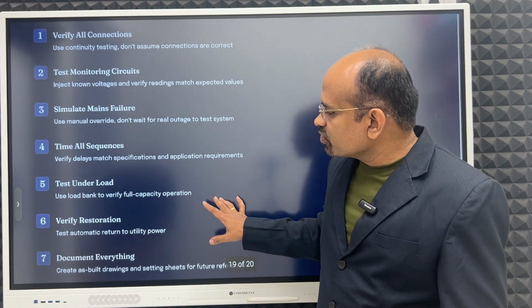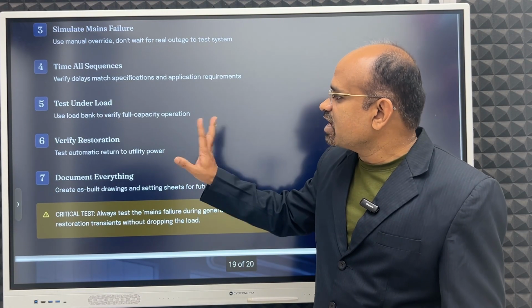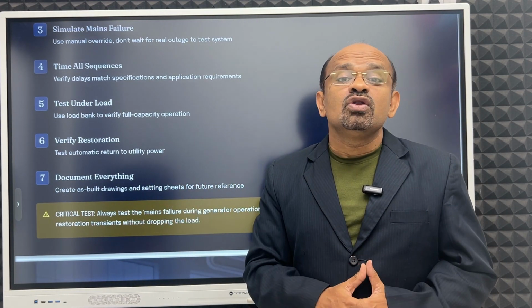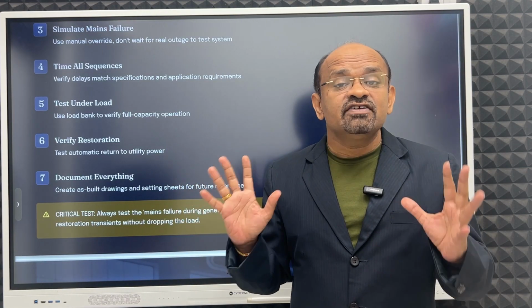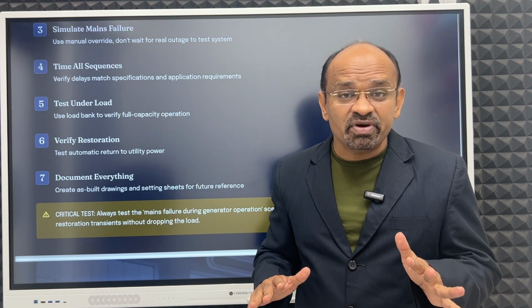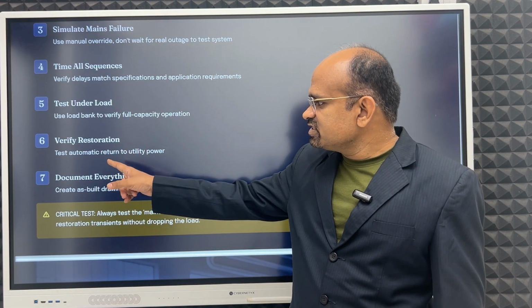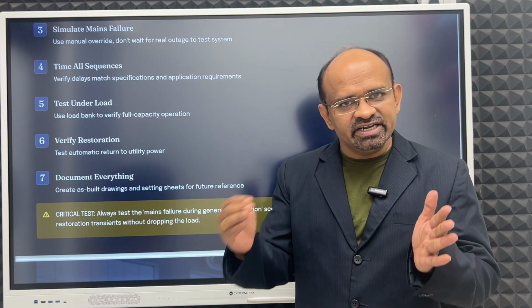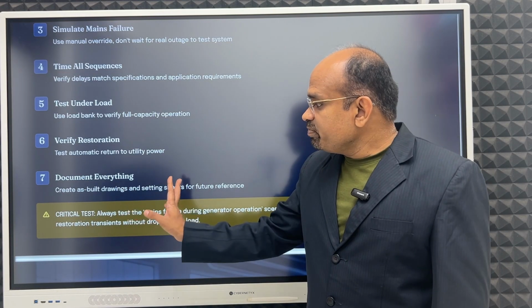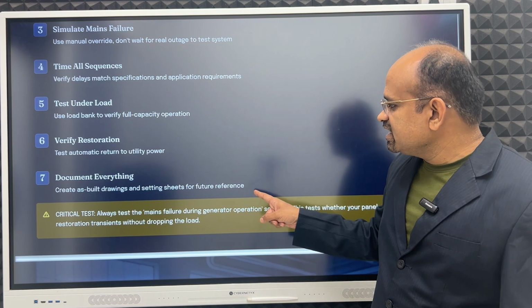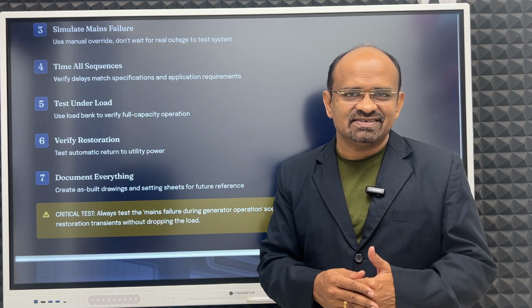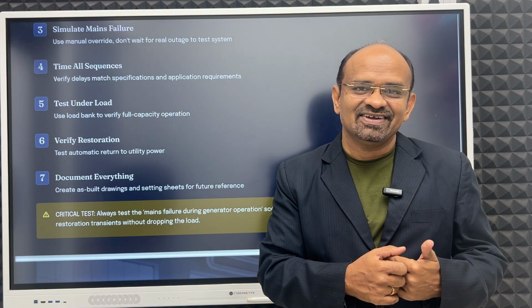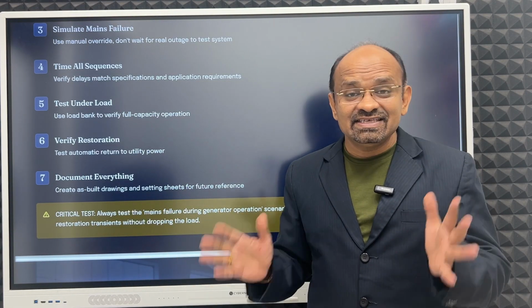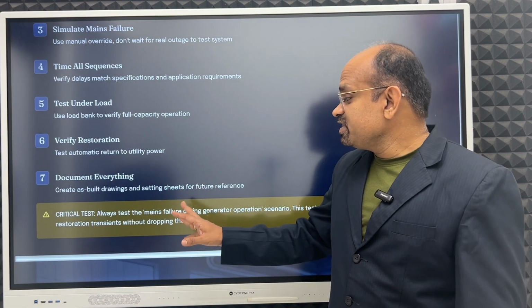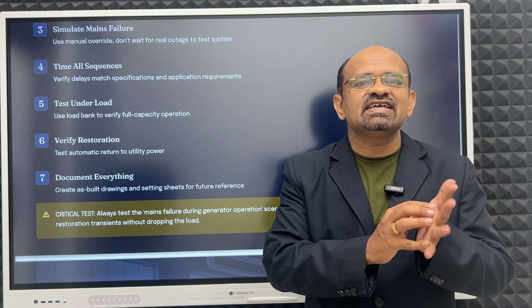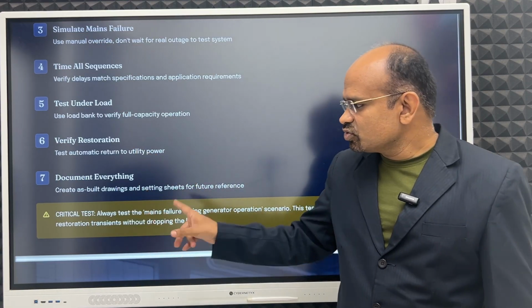Test under load. Use a load bank to verify full capacity operation. You should put it on the load bank so that we know at full load it works properly. So verify restoration. Test automatic return to utility power. Automatic return it should test. Document everything. Create as-built drawings and setting sheets for future reference, because technicians will keep on changing. Okay, attrition is there, so these physical records should be there. Drawings and setting sheets: what was the setting before at this particular load? So those should be there.